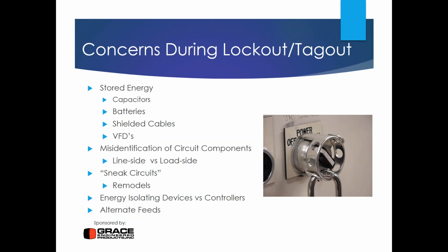That's the point of the battery bank. And they represent hazards both in terms of shock hazards, they also represent arc flash hazards, and they represent explosion hazards, especially if they're vented. Vented batteries often off-gas hydrogen, which is very explosive. Shielded cables are a very definite electrical hazard that must be taken into account because of stored energy. And by shielded, we mean that there is a metal jacket of some kind around the outside of the conductor. In most cases, on high voltage systems, this will occur above 5,000 volt systems. Historically, you are required to use shielded cable above that level. That is going to change in the code to 2,500 volt systems. So even your 4160 motor starters may very well have shielded cables on them in the future.